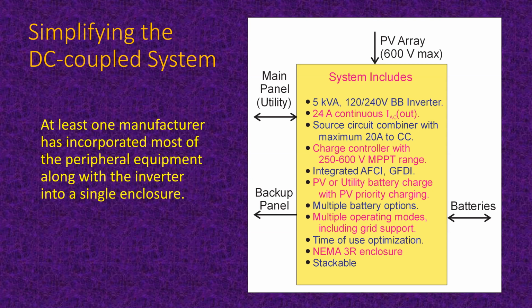There's a source circuit combiner with 20 amps to the charge controller. Actually, they now have a 7600 watt box that does 32 amps. The charge controller has a wide range of maximum power point tracking, integrated arc fault, ground fault, PV utility, battery charging, all that stuff that we had in about 5 different boxes is all in one box. And all you have to do is connect your batteries up to this.